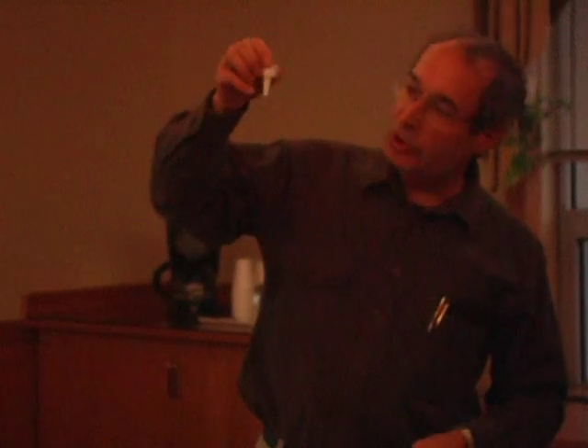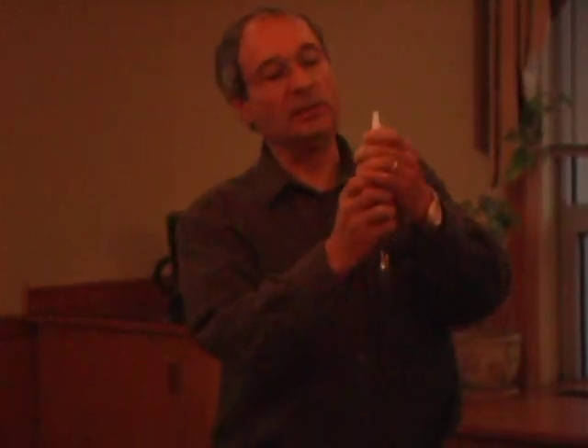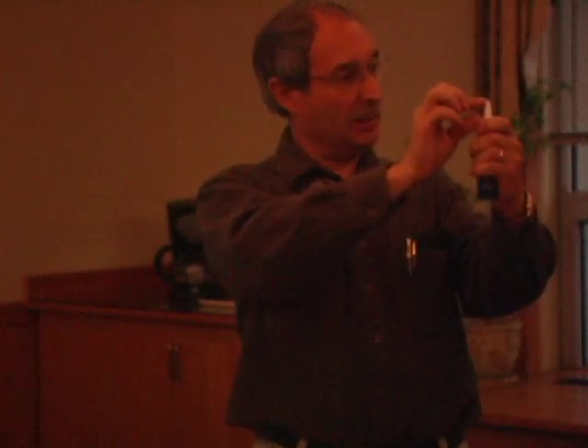Now, what affects the reading of this instrument is how accurate and careful we have been in placing the electrolyte inside of the membrane cap. If we have permitted a significant amount of air bubbles, that's going to impede the transference of that electrical current to the electrodes. The procedure that the manufacturer recommends, and I've done it, and it really works: first of all, on the top, I squeeze the bottle to get all the air out until I start seeing electrolyte coming out of the top.